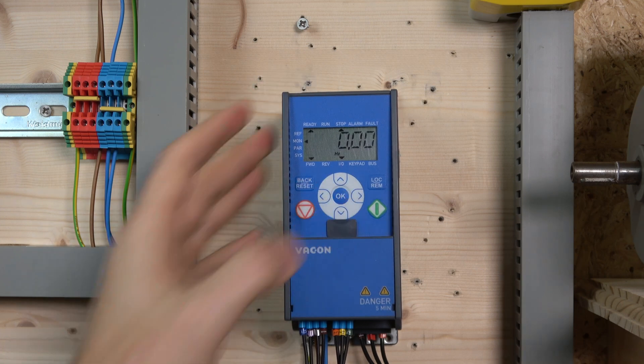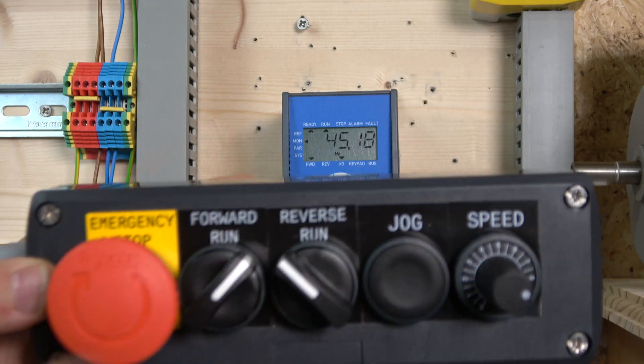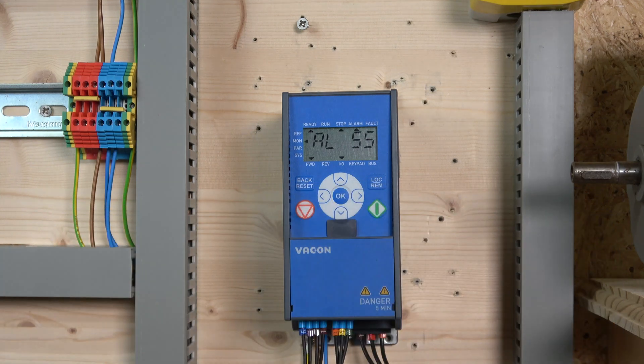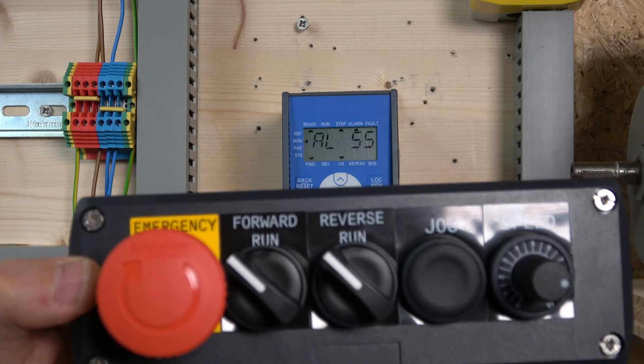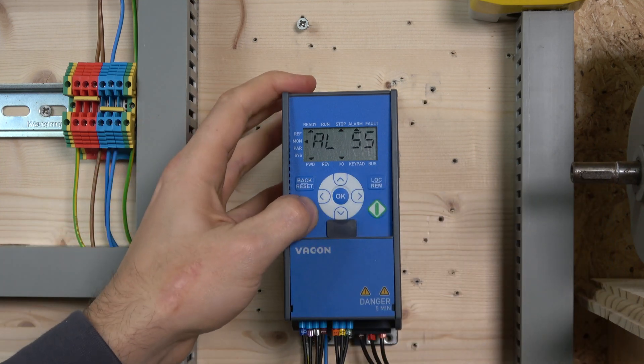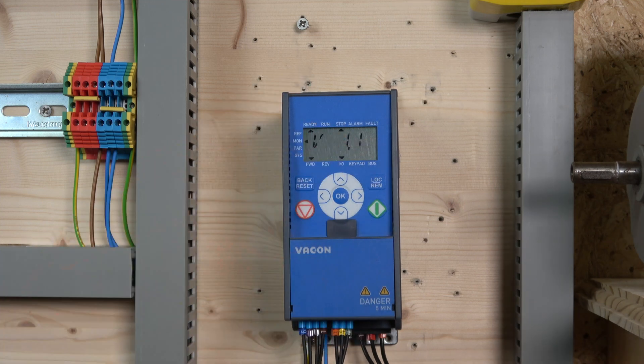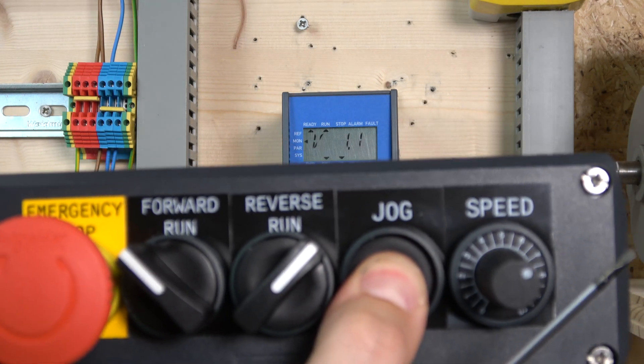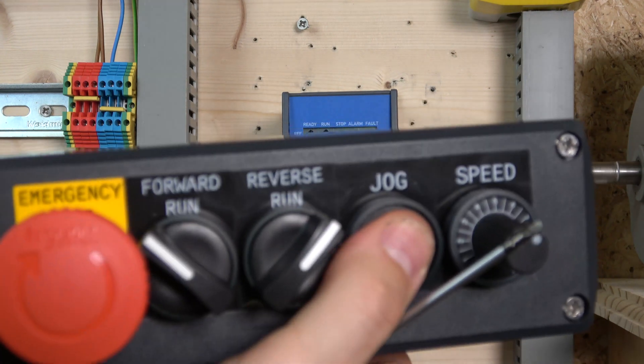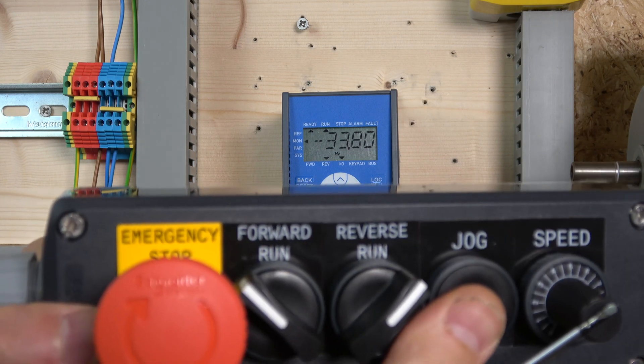Run forward - there you go. Adjust the speed. This is the first drive ever where alarm 55 comes up when you monitor. When you take it off, the alarm is still flashing. Click the stop button to remove the alarm. Then you can go in reverse. As soon as I push the jog, it will override any run signal and run at the preset frequency. That's it - two-wire control.